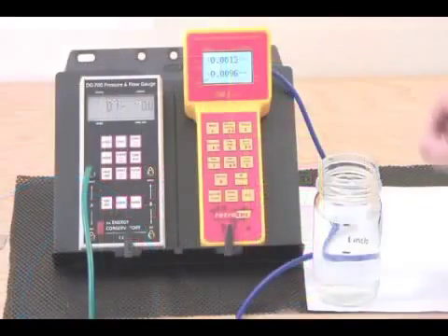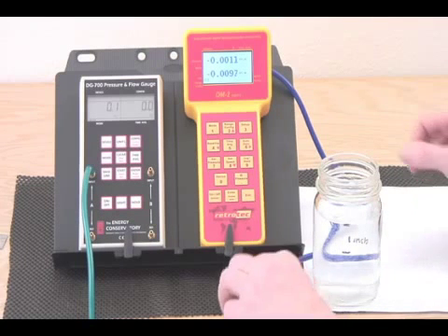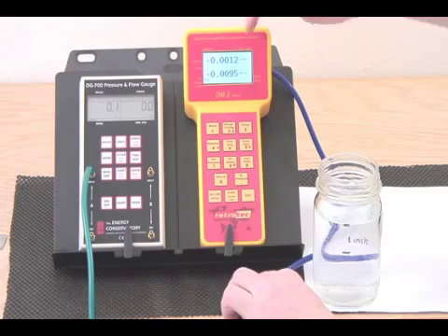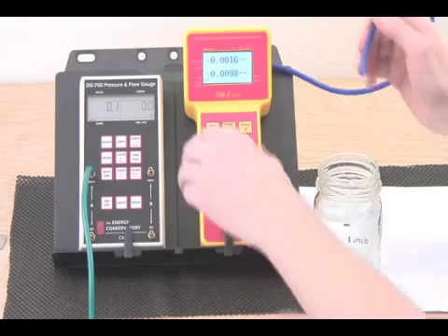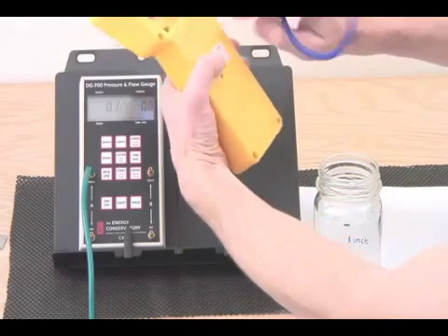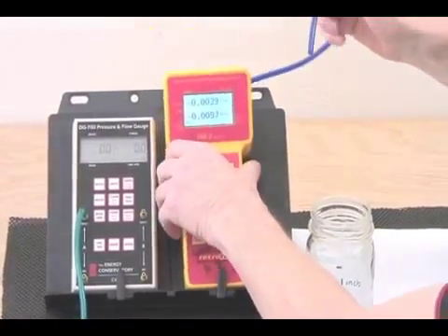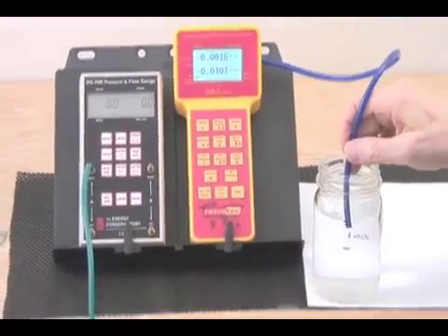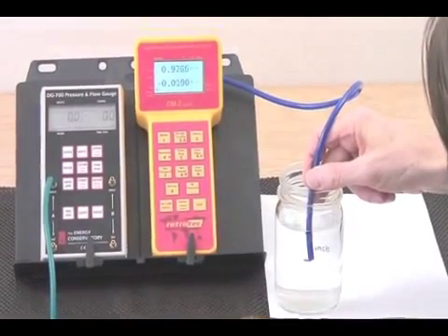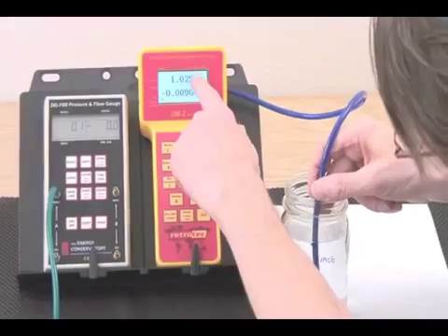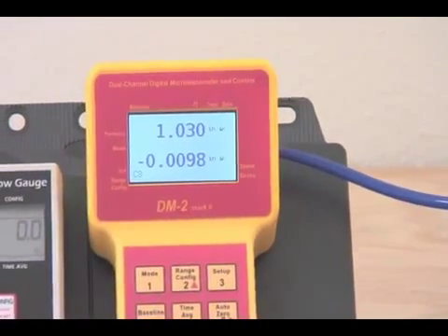negative. So here we have a little mason jar full of water, and we've got a 1-inch mark marked on it. This gauge is set to inches of water column. So we're going to take this tube that's attached to the positive port over here, or the input port on channel A, and we're going to submerge it down in the water 1 inch. So this gauge is now reading 1 inch of water column. It's exactly what we'd expect.